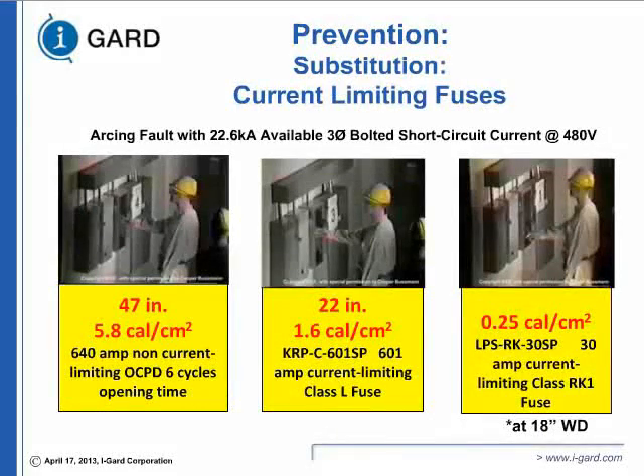These are some of the examples. If you have, for example, a non-current limiting fuse, what you see in the first slide at 47 inch is 5.8 calories. If you calculate that at 18 inch, you will have close to about 20 to 25. It's exponential. Now, when you have a current limiting fuse, if they operate in the current limiting range, you have 22 inch, about 1.6 calories. If you have a 30 amp fuse, you're looking at less than 0.25 calorie at 18 inch working distance. So basically, current limiting fuses and breakers, if they operate within the current limiting range, reduce the let-through current, reduce the energy, reduce the damage.